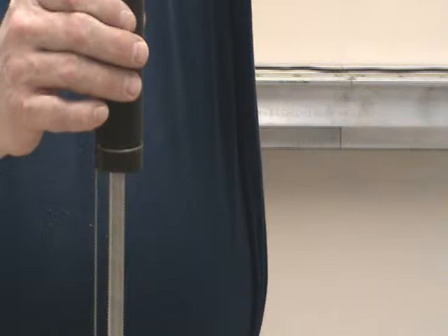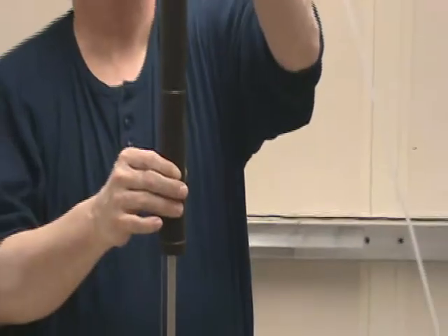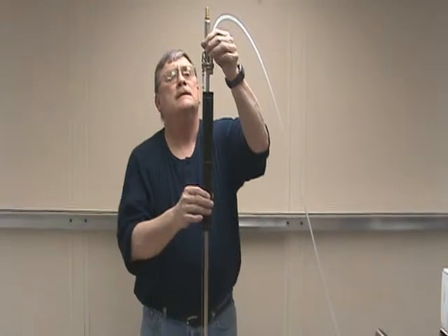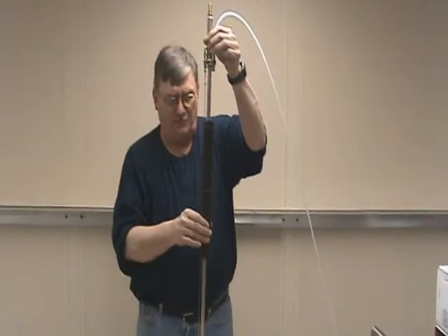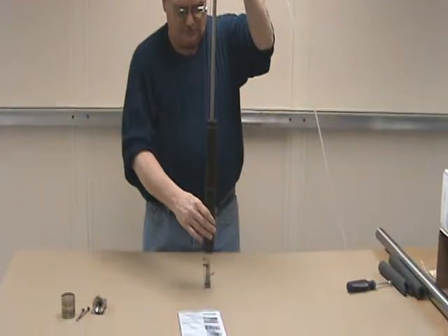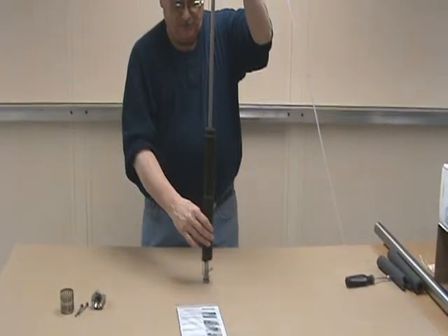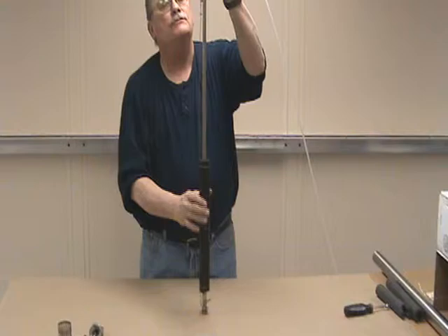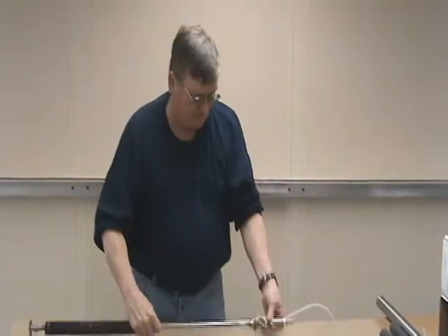We'll do this one more time. When the float comes up, the magnet will pull the valve open and air enters the pump. When the float comes down and touches the bottom stop, it pulls the magnets apart and the air is cut off to the inside of the pump.